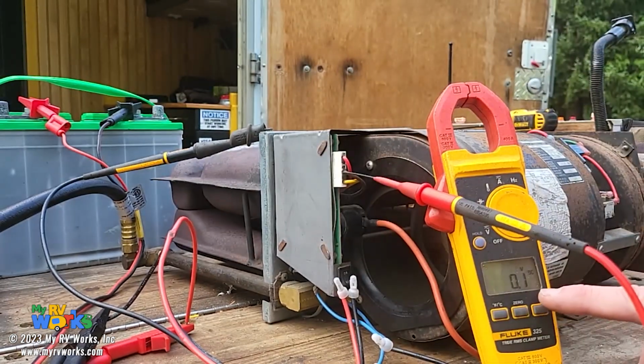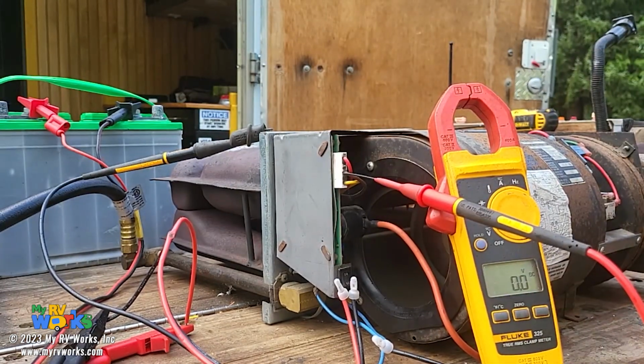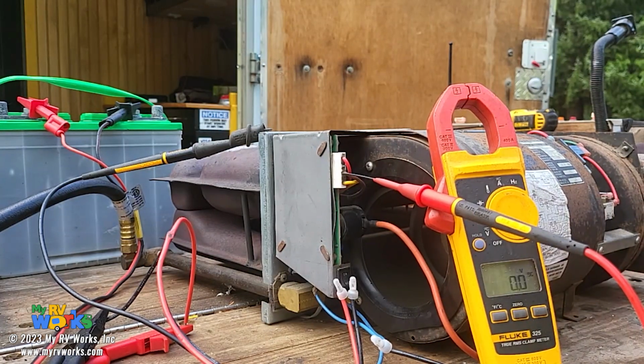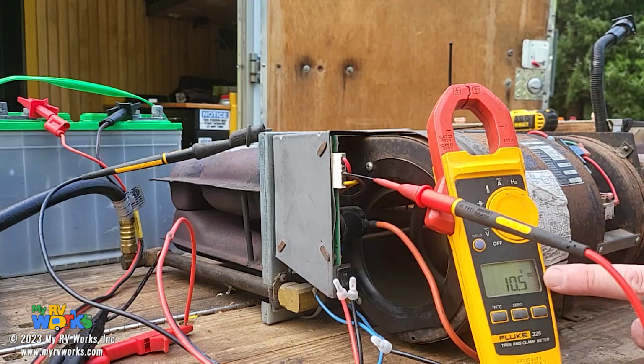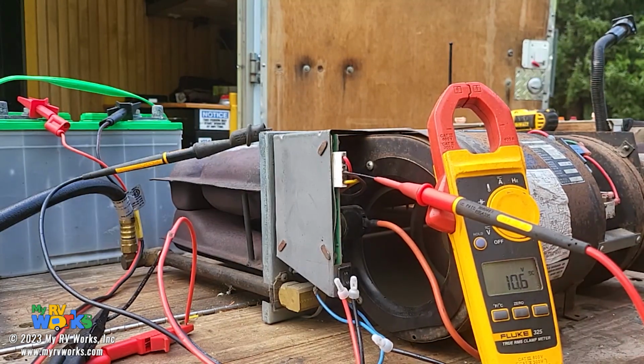So no voltage on the brown wire. The brown wire is my gas valve. Ignore the squealing, we're going to fix that. So we're going to look at the brown wire. There we go, and there was a click inside the board, and our voltage came on the brown wire, which is turning on the gas valve.